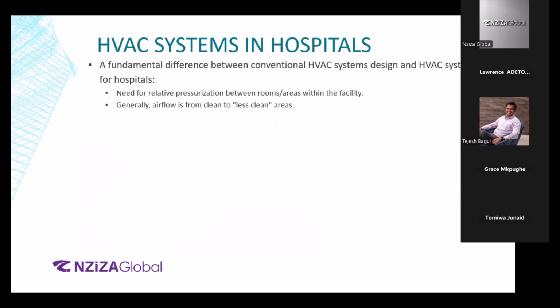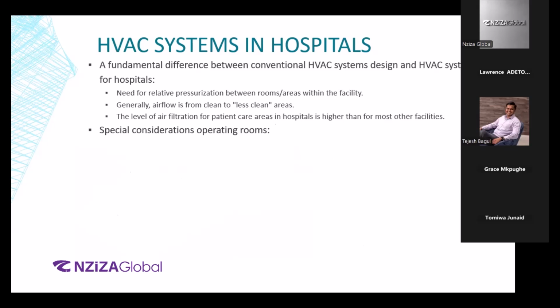So these are some of the fundamental differences. Okay, there were the conventional systems like, let's say, the hotel HVAC system, office HVAC system, but those are conventional. What we need in hospitals is far different. Why is it different? We need to maintain the relative pressurization between the areas. We saw the positive, negative, not required, right? So it is very critical for the hospital HVAC systems to maintain those. Along with that, the airflow is from clean to less clean area. We spoke about toilets, right? The air cannot go outside of the toilet. It needs to go inside of the toilet. Right? Clean to less clean area.